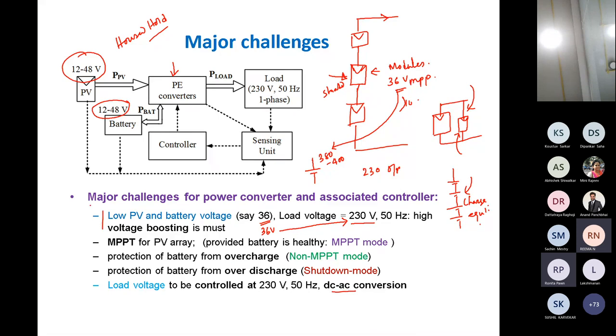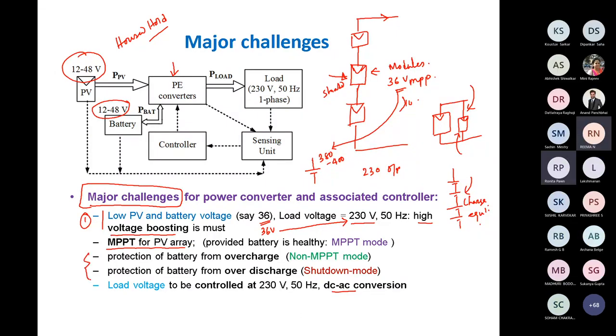So that is one of the major requirements. I have noted this down as a major challenge. If you want to design such a system: one, you need high voltage boosting, as I discussed. Second, I want to ensure as much as possible this MPPT operation - I want to operate my PV at maximum power point. Then I need to protect my battery from over-discharge and overcharge - I should not overcharge it, I should not over-discharge it. Then I need to control my load voltage at 230, because that is what the load demands. So all this we want to achieve, and of course we want to make the system low cost, higher efficiency, and those general requirements.